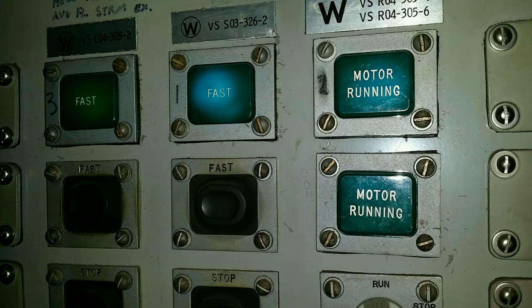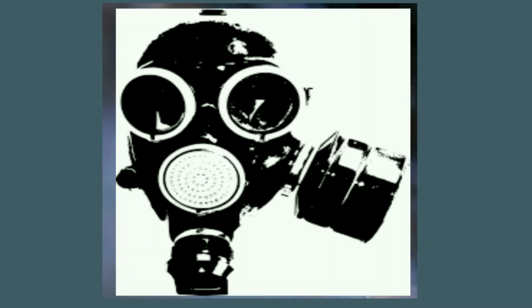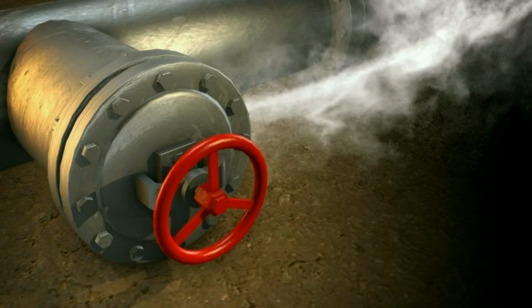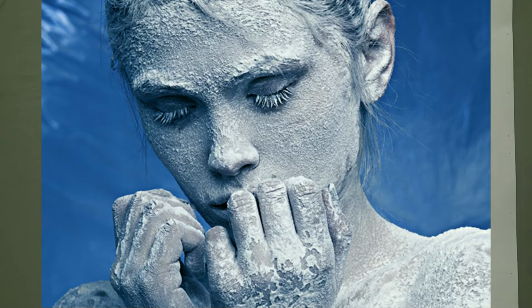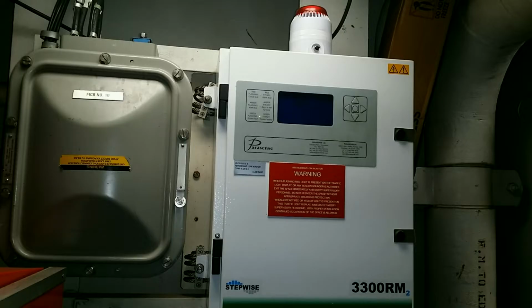I will also add that refrigerant in high concentrations, when you breathe it, is toxic by itself. In very low concentrations, if it's exposed to a flame or something that will make it too hot, it becomes very toxic right away. And if you're close to where the leak is at, it will cause you frostbite. So if you ever hear the halocarbon alarm go off, take it seriously. Now, let's continue.